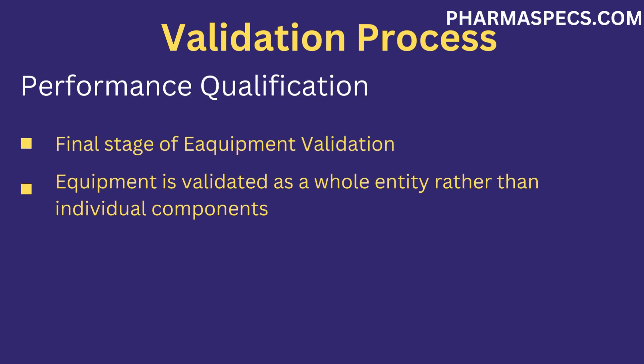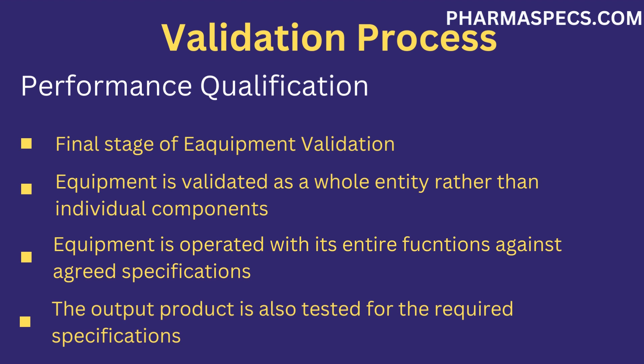Performance qualification is the final stage of equipment validation, and validation is concluded in this stage. In this stage, equipment is validated as a function of its product rather than by verifying individual functions. The equipment is operated with its full functionalities using actual product and packaging material if required. The output product is also tested for verification of the desired properties.